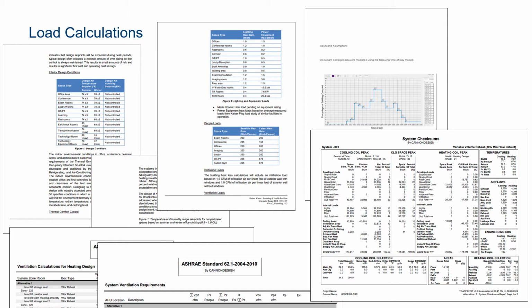One example is that engineers tend to get equipment lists of medical equipment, and then they read the nameplate electrical data, and they put in some diversity factors, and then use those in the load calculations. Well, we can't do that. That's crazy, because we have plug load studies. We know what the plug load signatures are for hospitals and clinics. We need to be using that data, not a theoretical diversity factor.